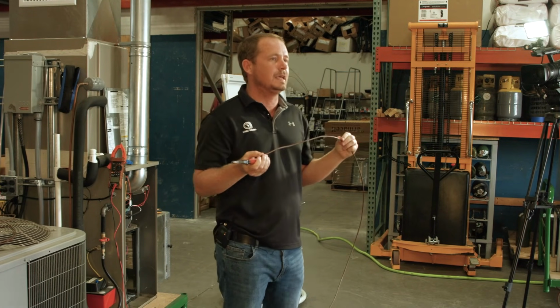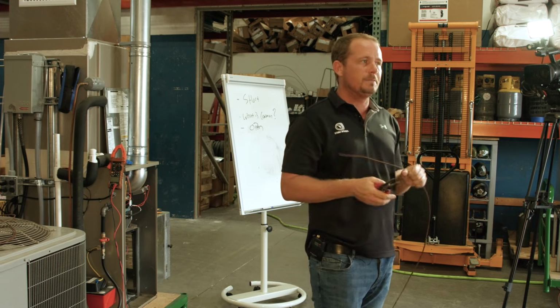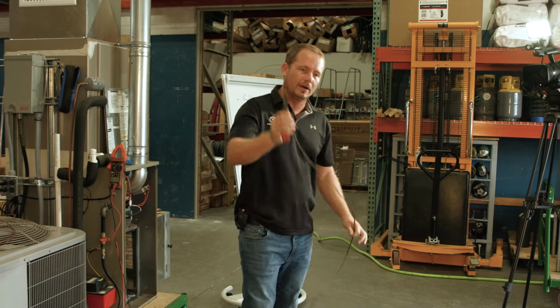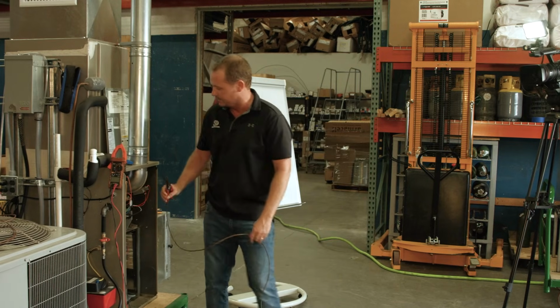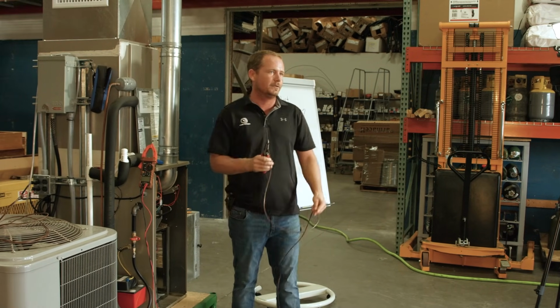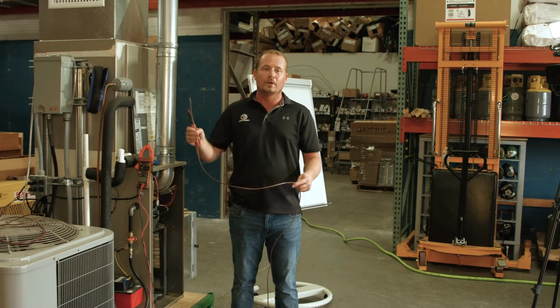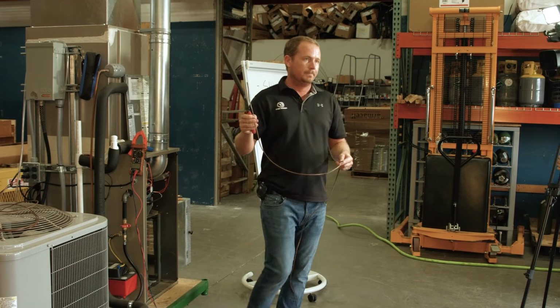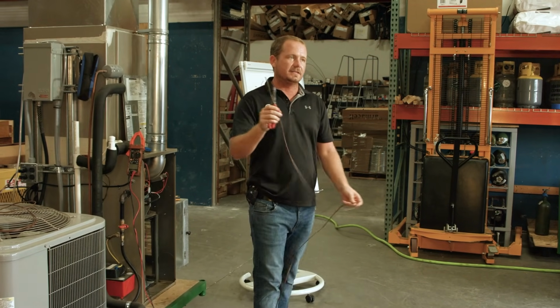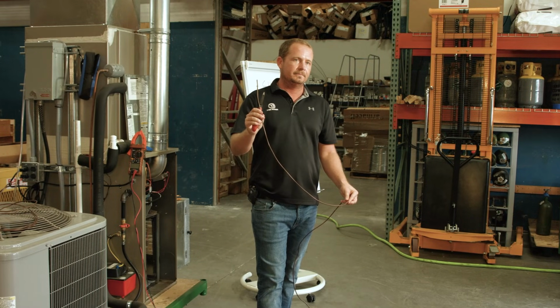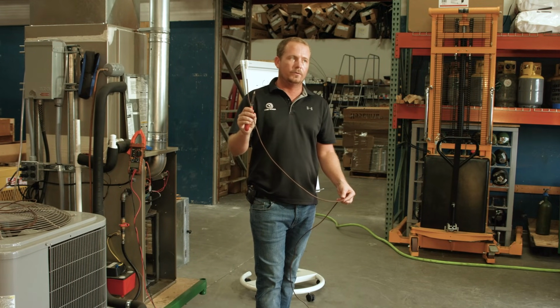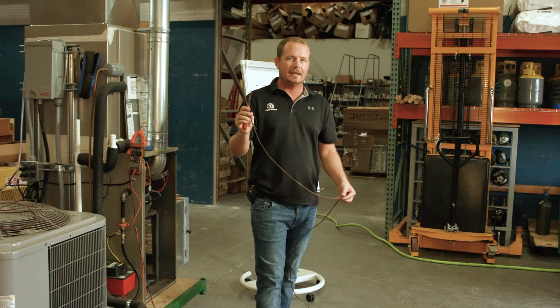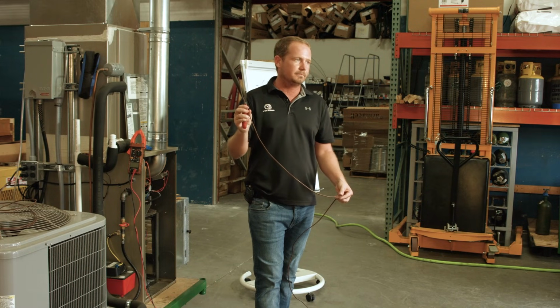Let's talk about a heat pump for a second. Pretend this is a heat pump. If I'm routing wires into it through where the evaporator is, I might think it doesn't matter if this touches the evaporator because it's cold. But in heat mode, that evaporator coil can actually get pretty warm.